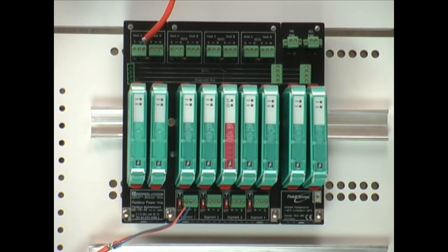Power supply's main goal is to provide a matching impedance for the field bus segment. If you just connected up a bulk power supply your communication signal would be lost and there would be no viable communication to control your plant.